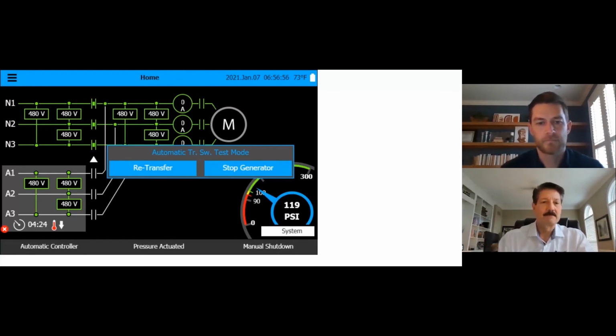The true way, as Cole mentioned, is kill power. You can kill power on the flange-mounted on-off switch on the normal side, or people just cut it off at the pole, or the pad mount, or the transformer from the utility will do it. But that is the best way to do it. When you're flowing at 150%, you need to make a transfer. That button is not designed to be under load at all. The pump is not going to run. It's just really for your testing to meet NFPA 25 requirements.